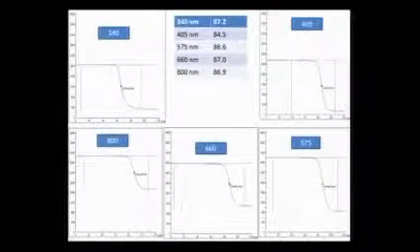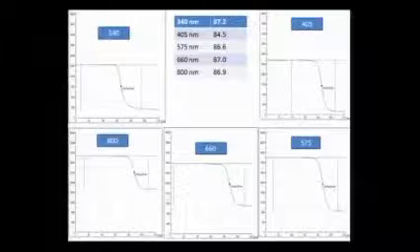So that means at 340, the clotting will be detected at a faster rate compared to 800, where the 800 takes its own sweet time to understand the clotting process and record the clotting very well. This can be useful when you have low fibrinogen or abnormal fibrinogen, where the clotting process happens very slowly, so that if suppose the clotting is not detected at 575 nanometers, it can immediately go to 800 and probably record the process, thereby not having that irritating message called no clot detected. It will definitely give you a clot.